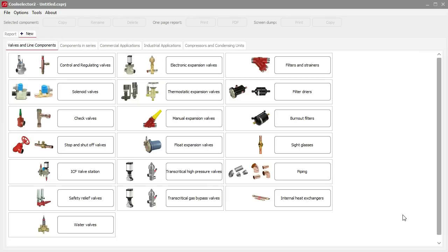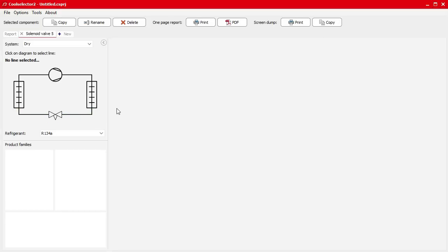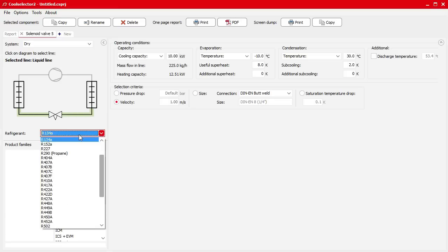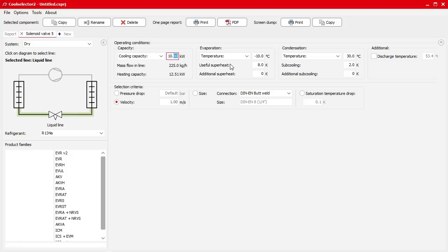The first design option is Valves and Line Components — this is for replacing a single component within the system or seeing how it might perform with a different refrigerant. Select the component you want, for example a solenoid valve, and it will ask whether you want it on the suction line, discharge line, or liquid line. Select liquid, then specify the refrigerant — I'll leave it as R134a — and it will ask about cooling capacity, evaporation and condensation temperatures, superheat, and sub-cooling.